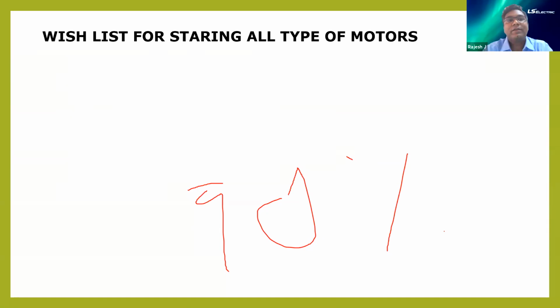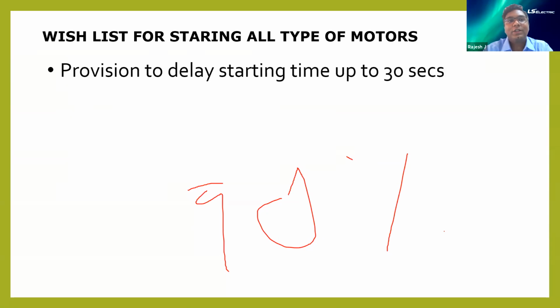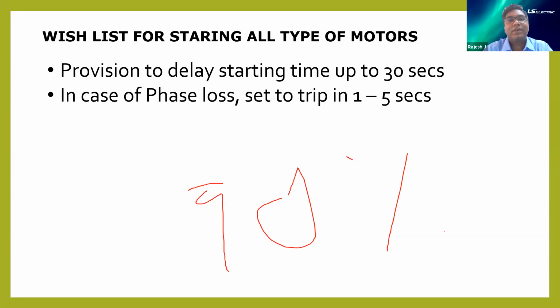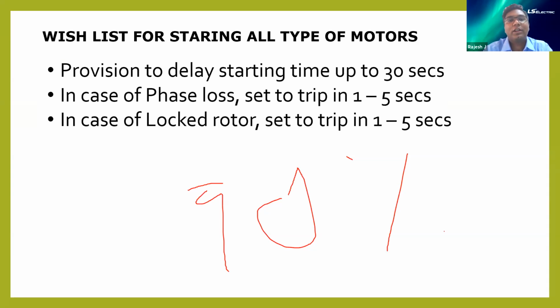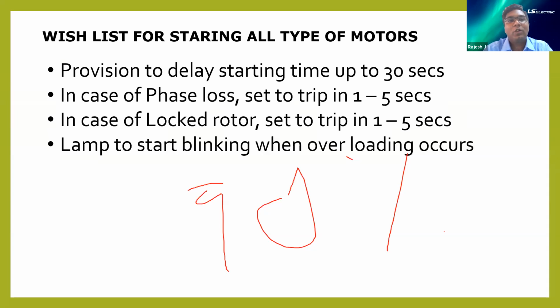Sure. Now it's a wish list for starting all types of motors. The wish list is a provision to delay the starting trip time up to 30 seconds, for example for a compressor or ID fan, where the starting inrush is more. To overcome that, the tripping time can be up to 30 seconds. In case of phase loss, set it to trip in 1 to 5 seconds for short-time phase loss. In case of locked rotor, you can set a trip between 1 to 5 seconds again.